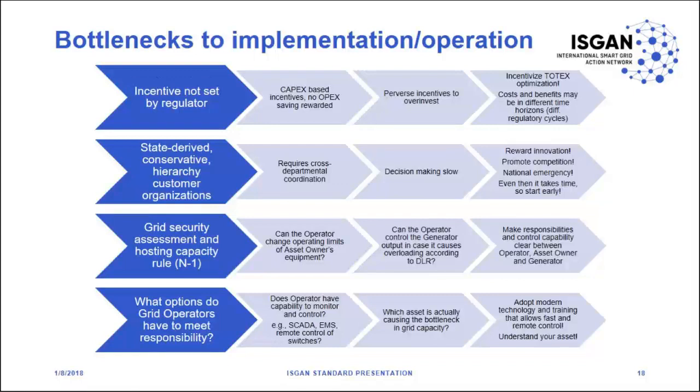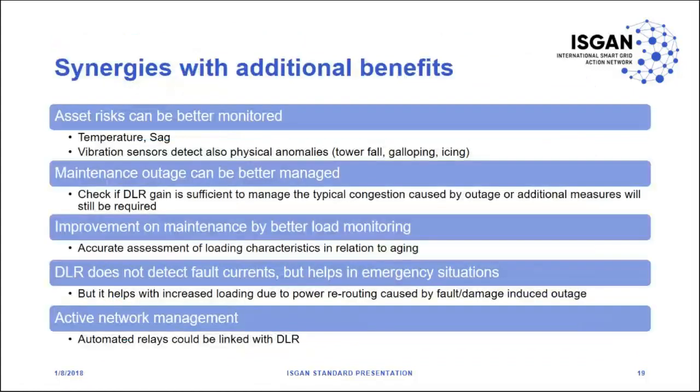What is the bottleneck then to deploy real dynamic line rating systems, like the ones supplied by Ampacimon? Based on our more than 10 years of experience, we can say that the major hurdles to adoption of these systems are not about the maturity of the technology or the reliability of the sensor systems. It's more about the way the incentives are set up for grid operators to really become active about driving down operational expenditure. So this can be in the form of a regulatory bottleneck, slow pace of coordinated decision making, and the methods used by and options available to grid operators to avoid potential overloads.